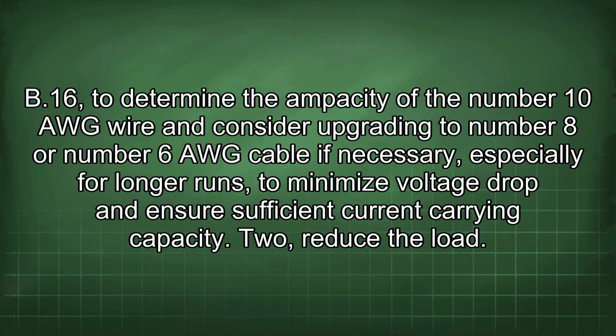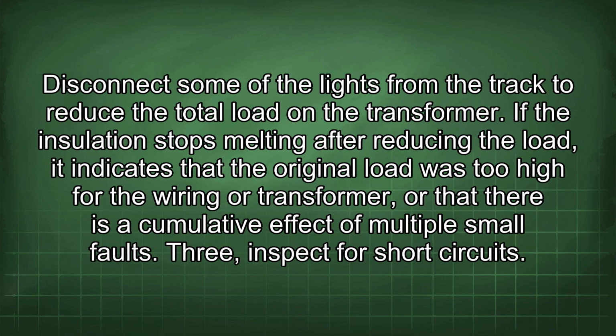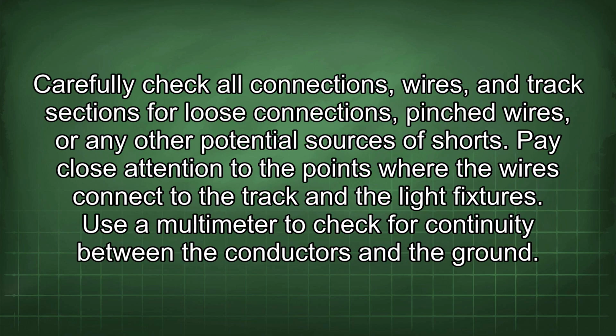2. Reduce the load. Disconnect some of the lights from the track to reduce the total load on the transformer. If the insulation stops melting after reducing the load, it indicates that the original load was too high for the wiring or transformer, or that there is a cumulative effect of multiple small faults. 3. Inspect for short circuits. Carefully check all connections, wires, and track sections for loose connections, pinched wires, or any other potential sources of shorts. Pay close attention to the points where the wires connect to the track and the light fixtures. Use a multimeter to check for continuity between the conductors and the ground.